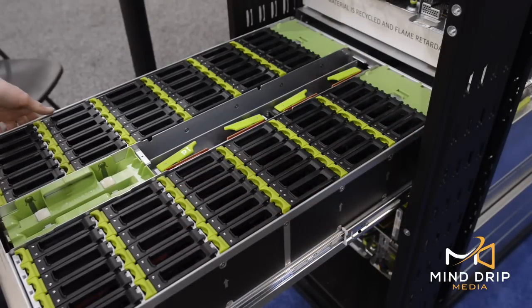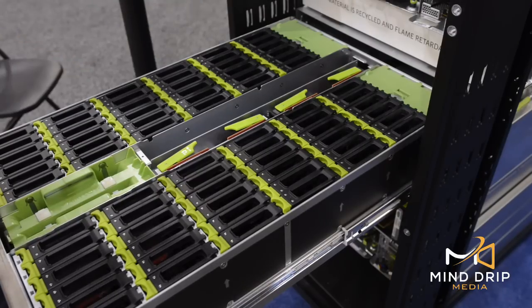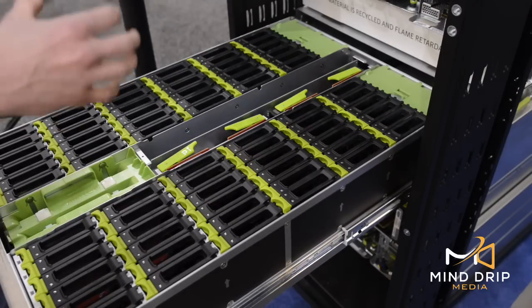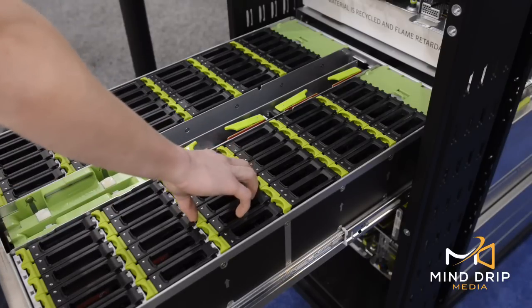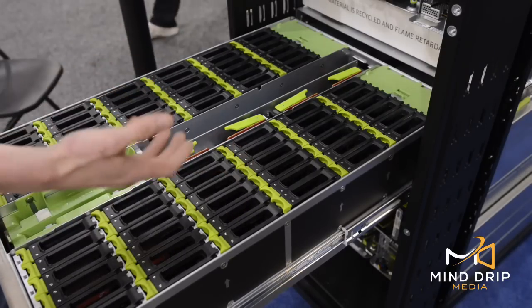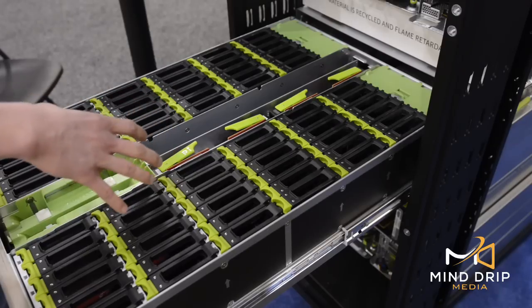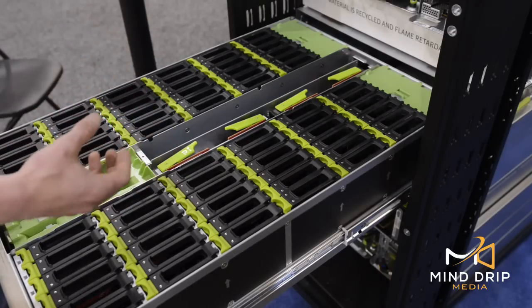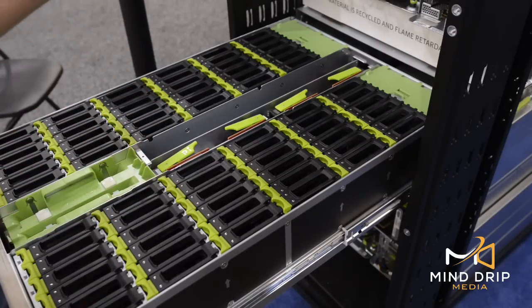Yeah, that's right. One of the goals of all the equipment here is to be able to have it as maintainable as possible while also preserving uptime. So in almost all cases, you can pull all the units almost completely out of the rack and service individual parts like swapping disks or swapping even PCIe cards and those sorts of things without taking the unit offline. Or in the case where you have multiple machines, which I'll show you later, you can pull one machine out of the tray without powering off the other machines that are also in that same tray.